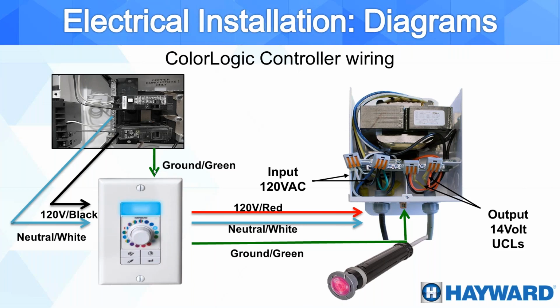We also always require a grounding for the controller. Then we're going to come out of the controller with our high voltage again, and we're going to feed the transformer. The transformer in this case obviously needs to be 120 volts with a neutral wire. And then from the transformer, we come out with the 14-volt line, and that low voltage 14 volt is how we're going to feed our ColorLogic lights. So keep in mind that the controller is always high voltage, and from there we feed the transformer in order to get the low voltage into the lights.